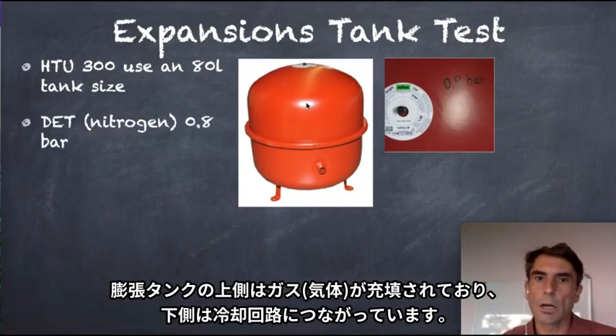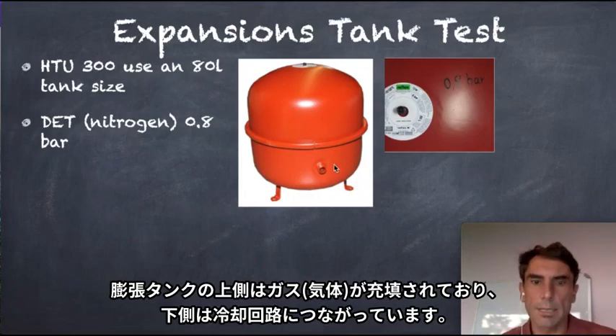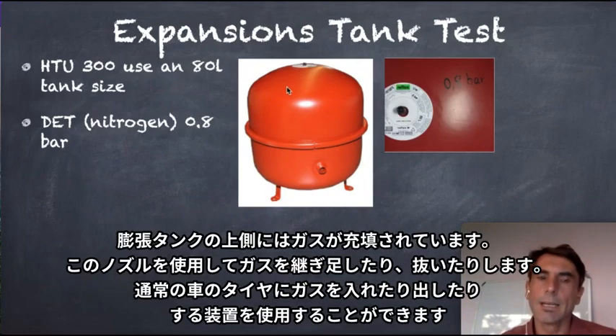Okay, and here on the gas side, that means here we are connected to the water side. So the one side of the expansion tank will later be connected to the water side, for example here to the HTU unit. The other side is a gas. So it's nitrogen gas, which can be filled and measured here on top on that valve. There's a valve like a usual tire valve from the car. So we can measure the pressure here and can release or fill up the pressure.